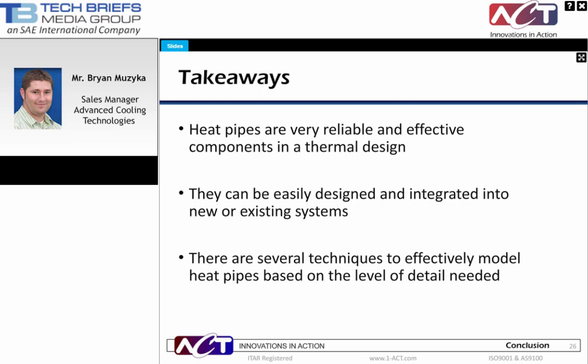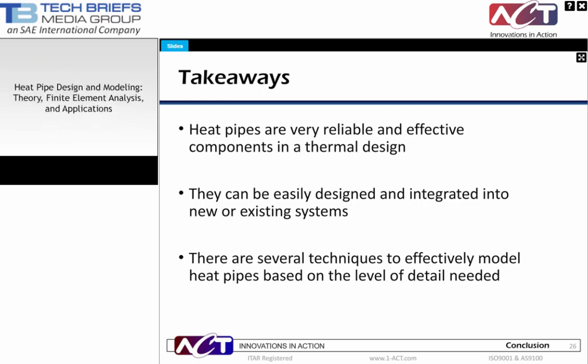Thanks, Brian. This is Billy Hurley with Tech Briefs. At this time, we'd like to begin our Q&A and welcome to the line Jens Wyatt, lead engineer for the Defense and Aerospace Group at Advanced Cooling Technologies. The first question: how thin of a bond layer is required, and what is the approximate conductivity of that layer? Typically, we like to see two-thousandths to four-thousandths of an inch clearance on the radius of the pipe. For example, for a quarter-inch diameter heat pipe at 0.25 inches, we would like to see a groove about 0.255 inches. As for the conductivity, solders range about 40 watts per meter K, whereas a lot of epoxies are about 1.4 to 4.5 watts per meter K.